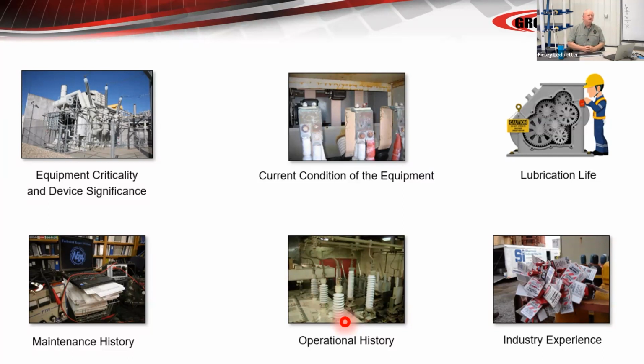Current condition of the equipment: is it clean? Is it dry? Is there water infiltration, bugs, spider webs, snakes, mice, all the things that kill the switchgear? Do you see any of that? Make sure you're using proper lube. Make sure you're cleaning the material before you relube it. Don't mix incompatible lubricants. Never use a spray can with a light lube on anything mechanical. Be very careful washing out all the grease and getting some light lube in its place, because in a few months you're going to have a failure.